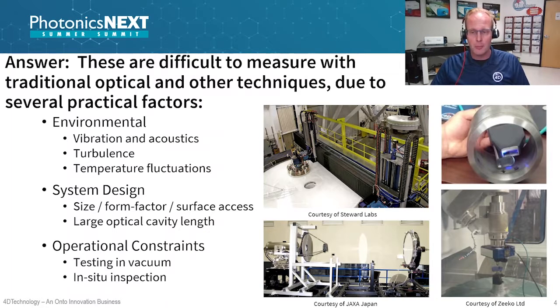As well as in situ inspection, where you're in a fab or process line, polishing an optic or cutting a precision machining surface, and you need to look at the finish as you're going. You need to measure in line in the process. A lot of access points, a lot of vibration, and things to consider. So typical interferometers, where you need an isolation table or minimized airflow and a very quiet environment, are very impractical or in some cases impossible to use with typical methodologies.